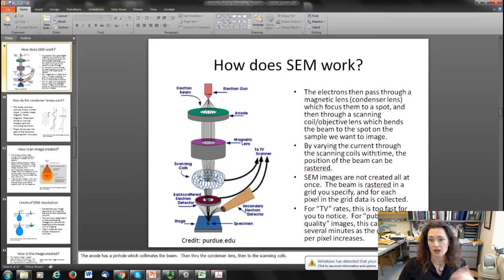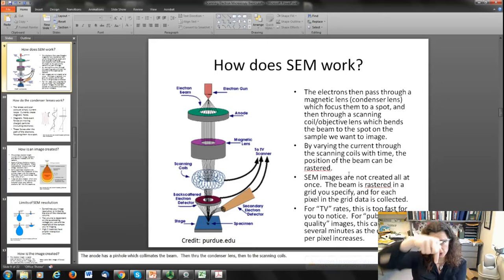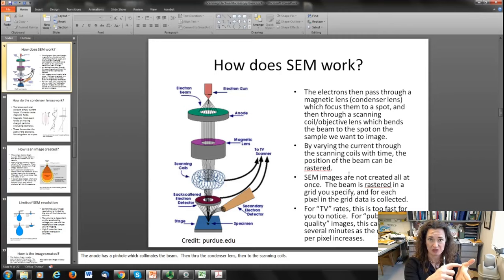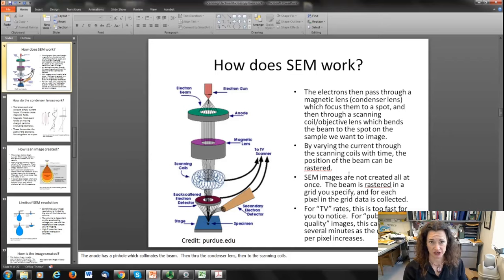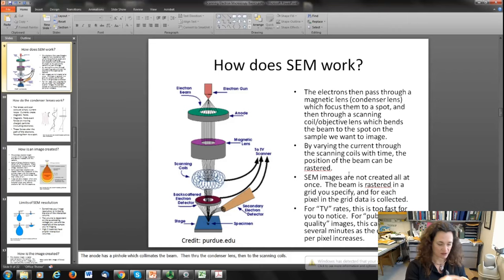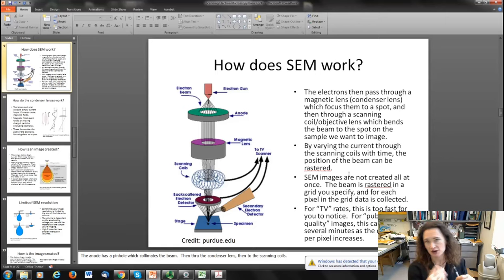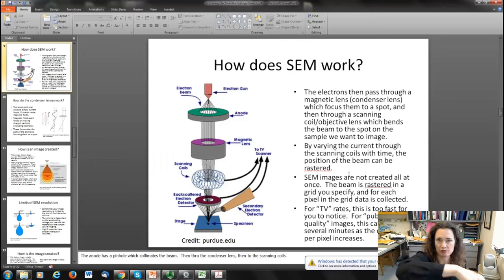SEM images aren't created all at once. What happens is you focus your electron beam down to a spot and then scan that spot back and forth across the sample in a rectangular raster pattern, kind of like an old school television set. The position of the electron beam at various times is taken as the pixel, and you monitor what signals come out at each pixel, generating an intensity map for whatever signal you're looking at and creating the image. When raster scanned at a fast TV rate it's too fast to notice, but for a really nice high quality image the scan will be slow and takes several minutes.